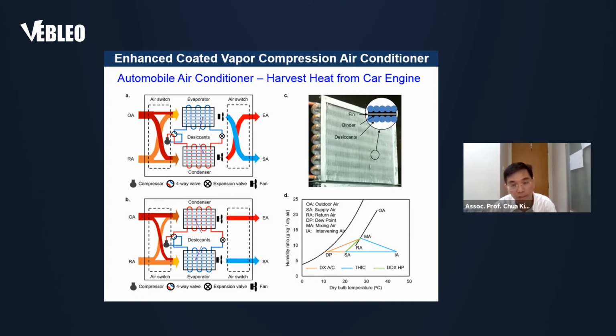Now you can cool the air at about 15 or even 18 degrees C. The reason the refrigerant previously needed to be at 5 to 6 degrees is that it needed to condense the moisture from the air. By coating this material on the heat exchanger, it doesn't need to remove the moisture anymore - it just needs to sensibly cool the air. So it can operate at a much higher temperature, about 15 to 18 degrees, compared to previously 5 to 6 degrees.